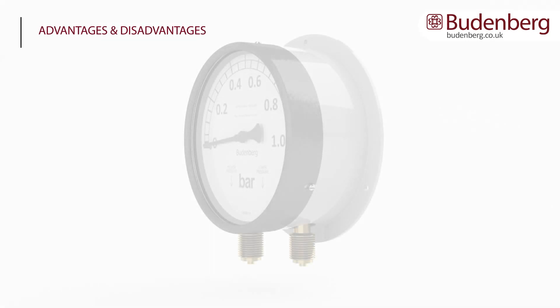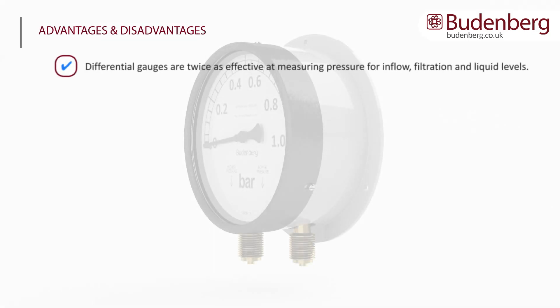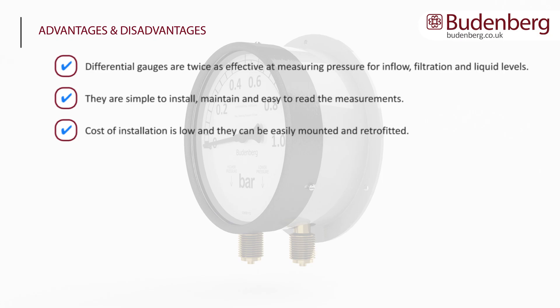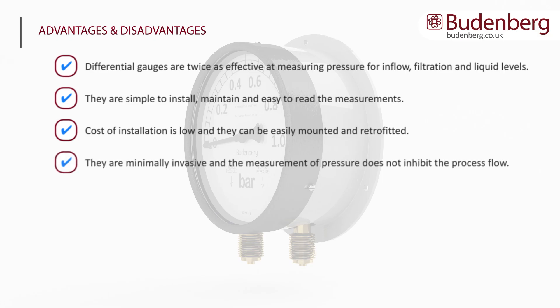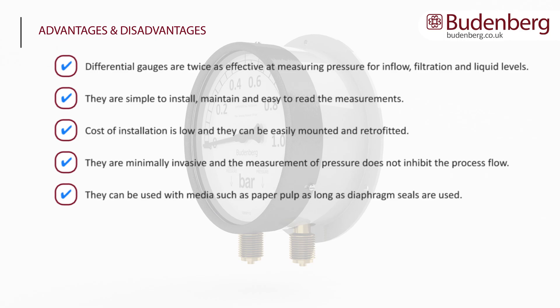Advantages and disadvantages: Differential gauges are twice as effective at measuring pressure for inflow, filtration, and liquid levels. They are simple to install, maintain, and easy to read. Cost of installation is low and they can be easily mounted or retrofitted. They are minimally invasive and the measurement of pressure does not inhibit the process flow. They can be used with media such as paper pulp, as long as diaphragm seals are used. A disadvantage is that an error may occur due to temperature fluctuations.